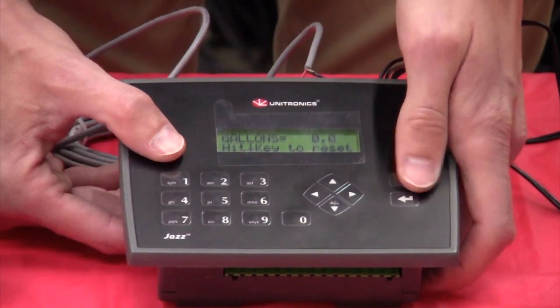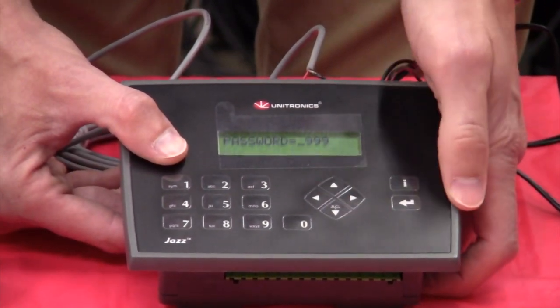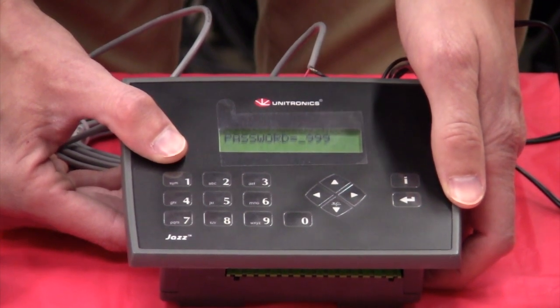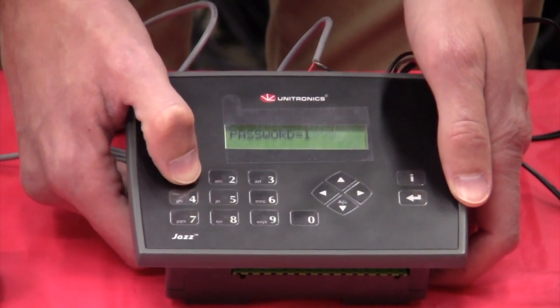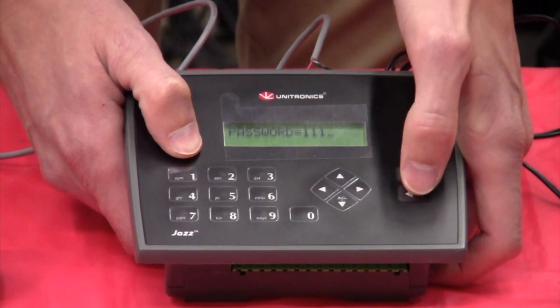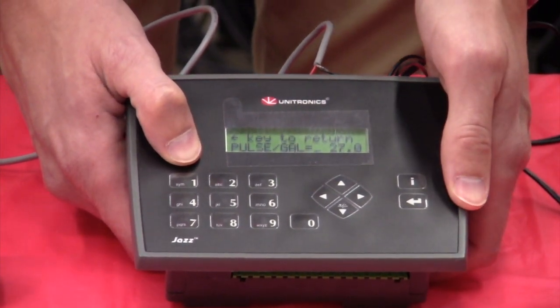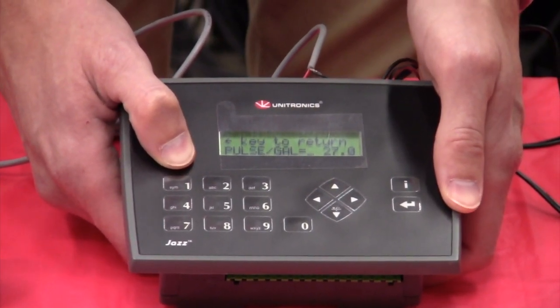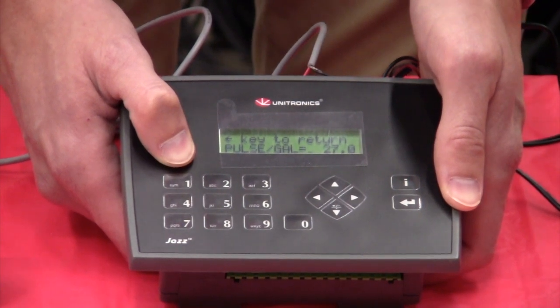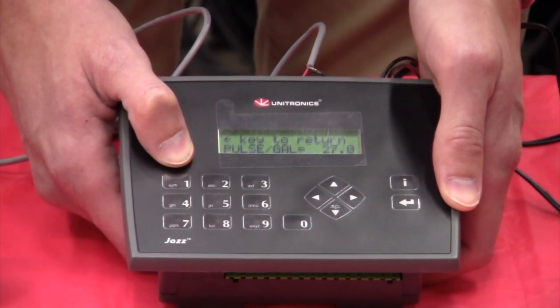I will also show you, if you want to get into the programming feature, you hit the up arrow, then we type in our password, which is 111. We hit enter, and this is where we can set our K factor. The K factor is what we will use for calibration, which is the next step that I will show you.